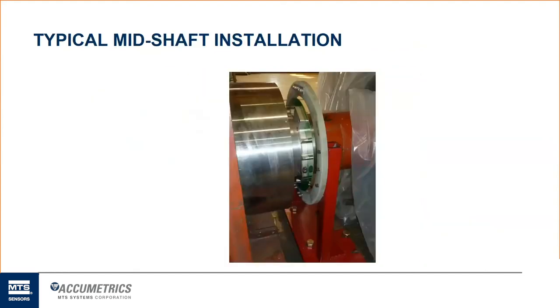So here's what a typical mid-shaft installation may look like. Again, this is the coupling flange that is going to mate up to the generator, which would be off to the left, which would have an identical coupling flange, and then they get all bolted together. So you have to be able to get the electrical bus connection, the negative and positive side of the field, from the exciter over to the generator. And this is how they decouple it from that. I'll show you in the next few slides how they get that electrical connection.